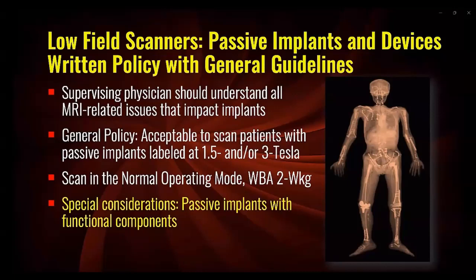To ensure patient safety, a margin of safety may be provided by operating the MR scanner in the normal operating mode, which defaults the whole body average specific absorption rate to a value of 2 watts per kilogram.